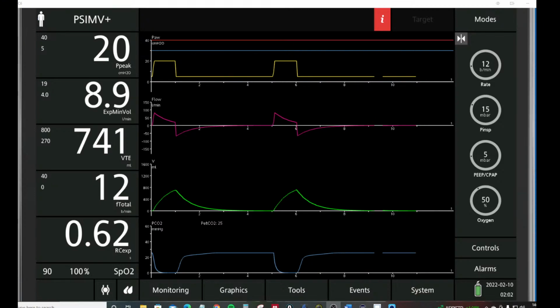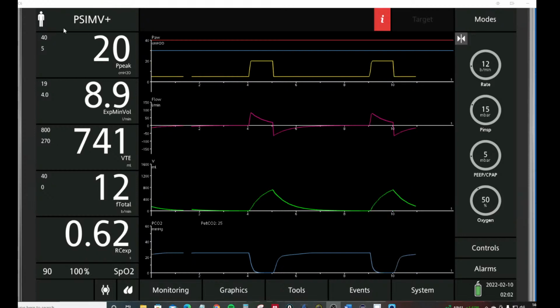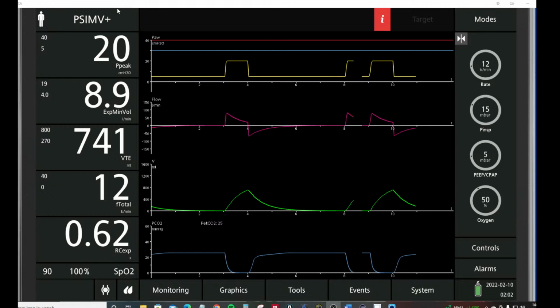So this is the Hamilton ventilator screen, like I say. Now, there are a number of features that are fairly consistent with most ventilator systems. So firstly, you can see up here at the top is the mode that the ventilator is in. Now, a lot of ventilator companies have different names for the same mode, so it can become a little bit confusing.